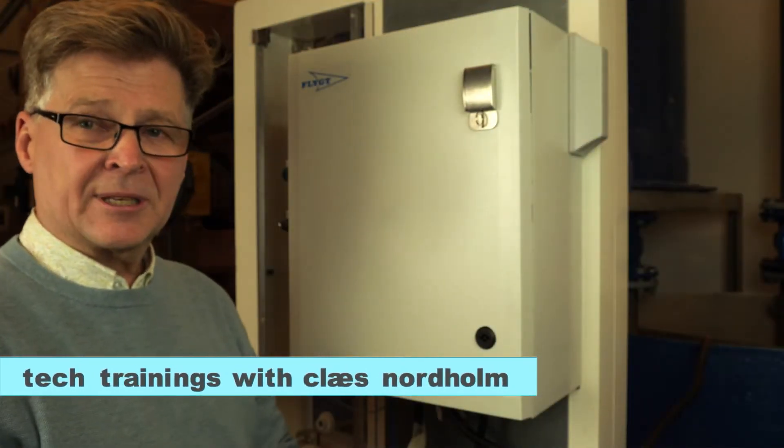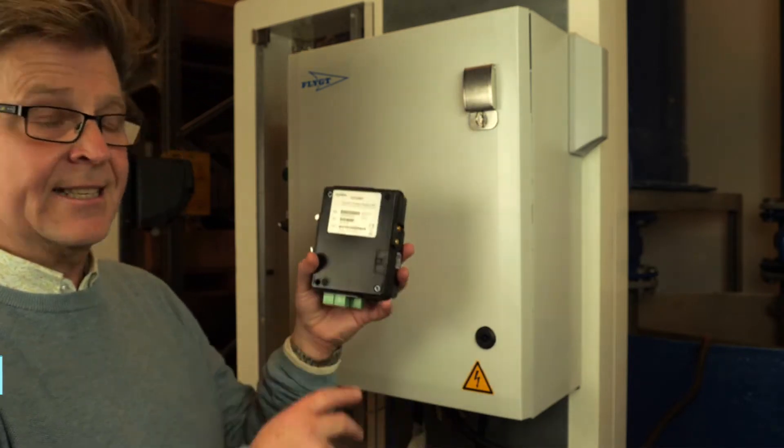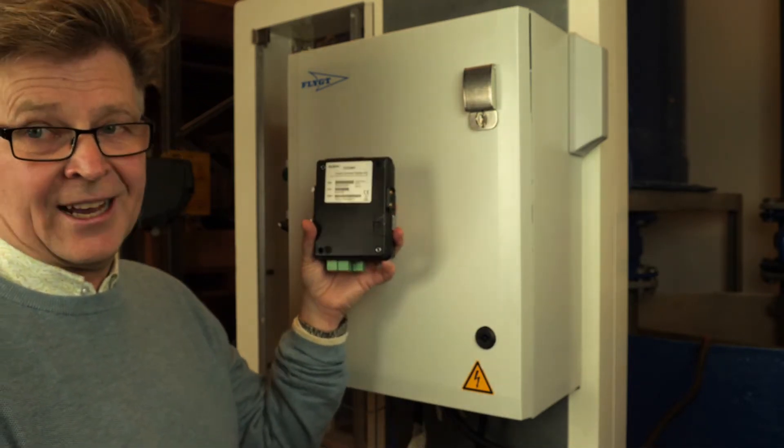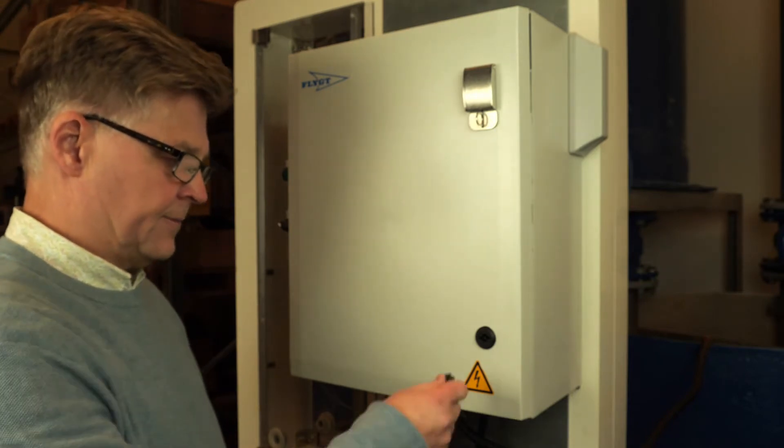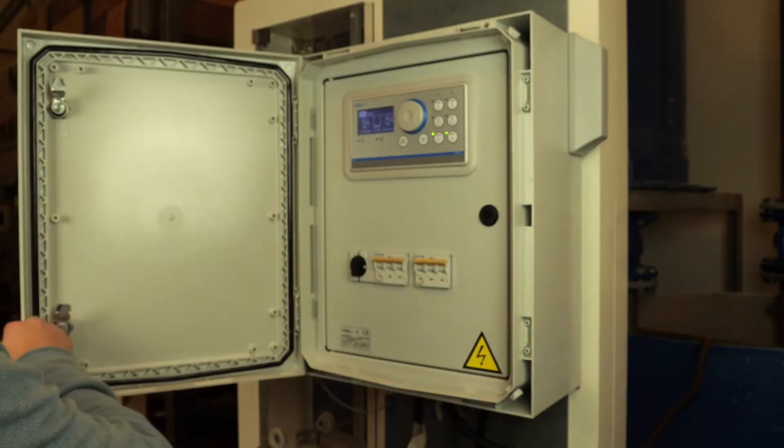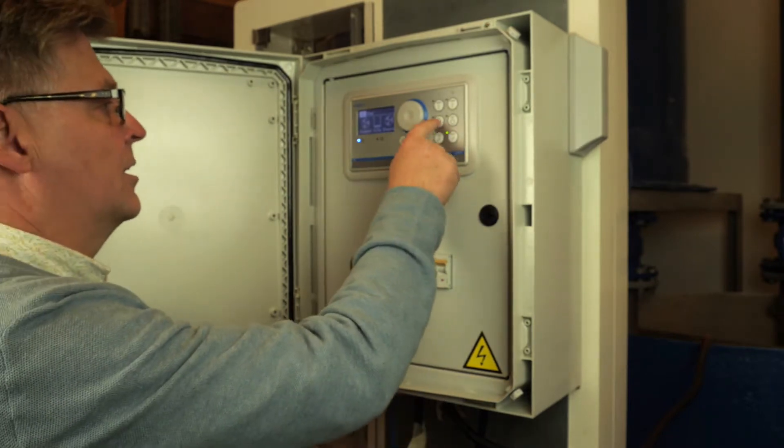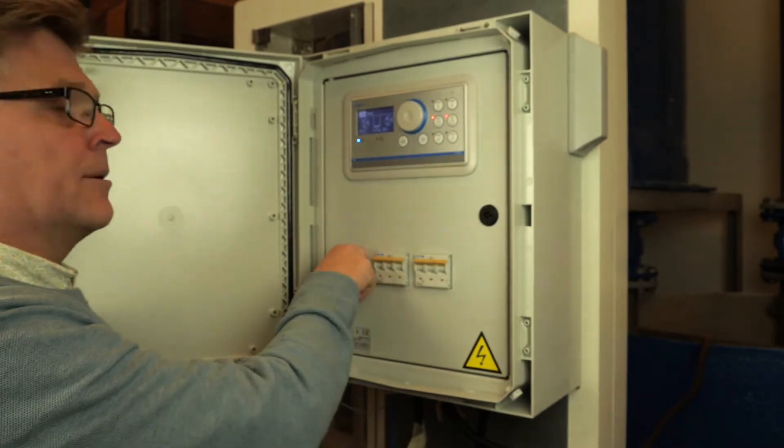We are going to equip this pumping station cabinet with the CCD-401, the Cloud Connect device. So what we do is open our cabinet door and we turn off the pumps and main power off.